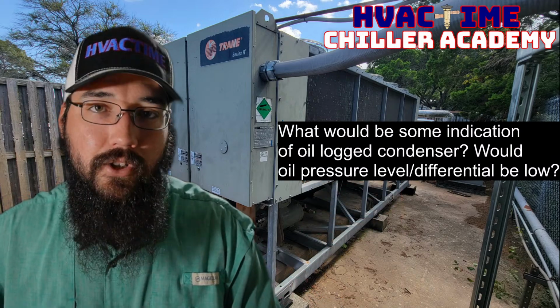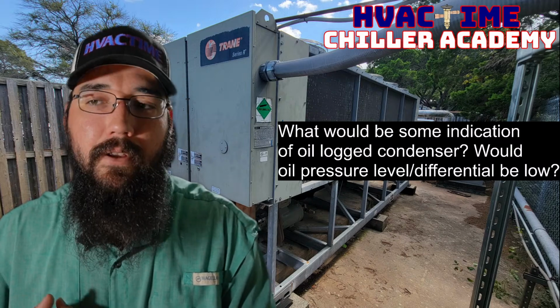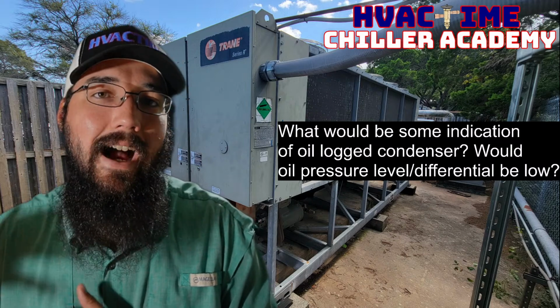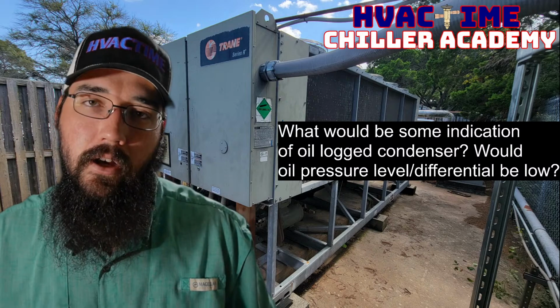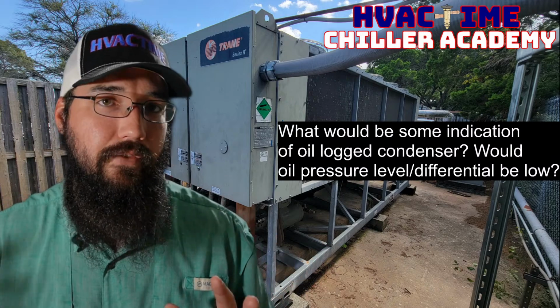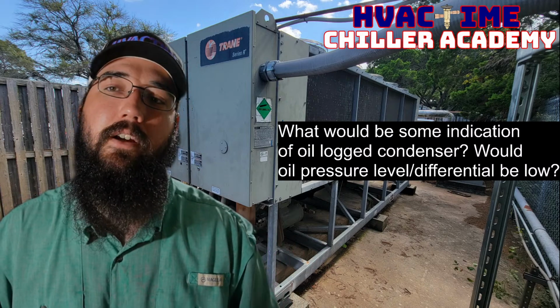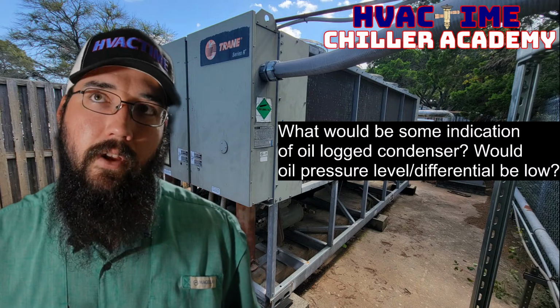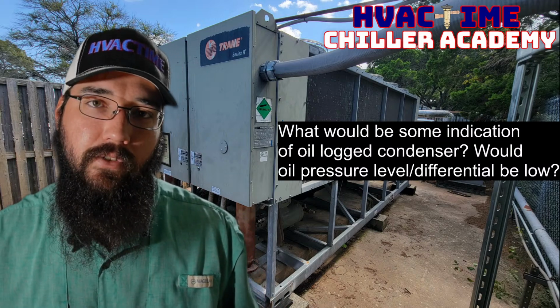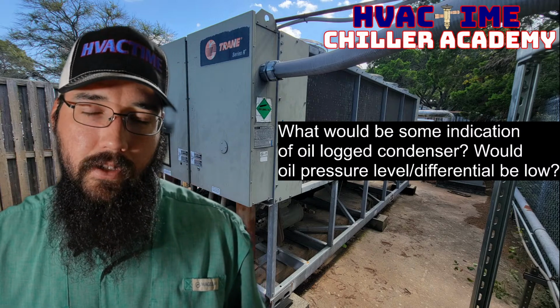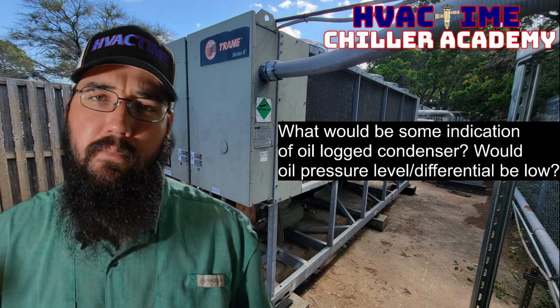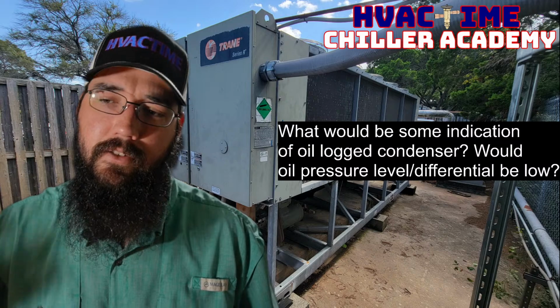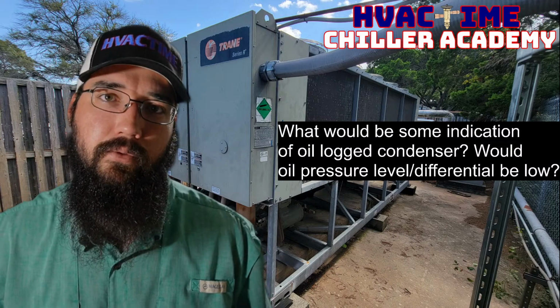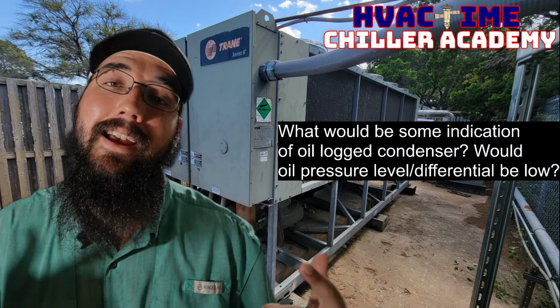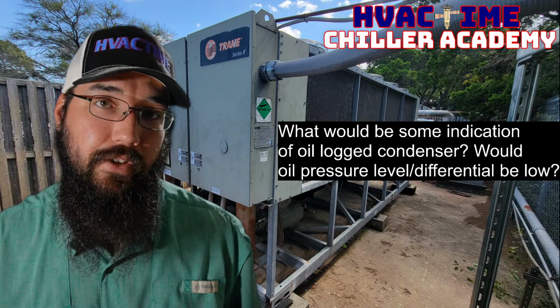What that will eventually do is lead to higher head pressures. Now, that is kind of a self-correcting effect on an air-cooled machine, because if the reason we're struggling with velocity in the first place is cold condensers, then less heat exchange is going to heat up our condensers, and it's going to push its way through, and eventually it may hit this tipping point. What it will do, though, is it'll be far less efficient.